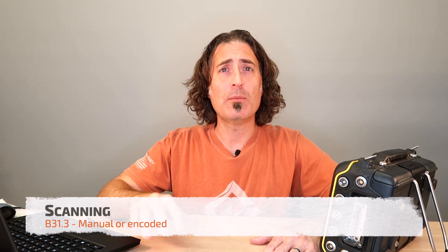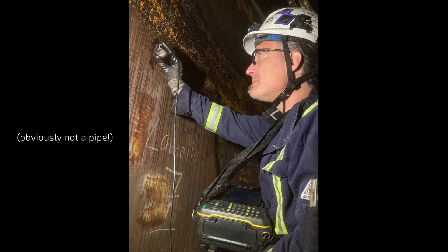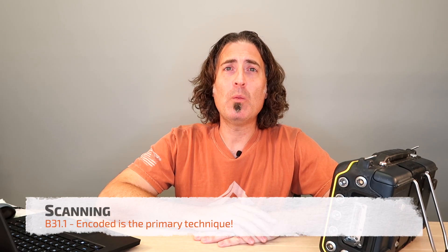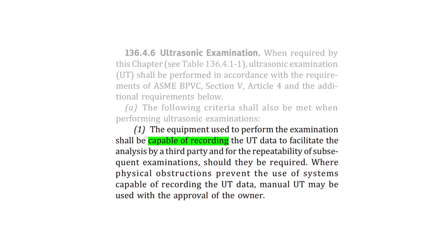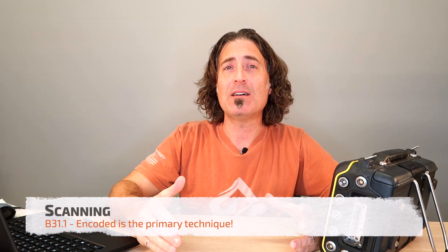Let's talk about hand scanning versus encoded. For B31.3, that's the easy one — they're actually going to let you hand scan with conventional UT or phased array, but typically what you're going to do is an encoded phased array scan. For B31.1, you have to encode. The only time they're going to let you do any hand scanning at all on a B31.1 piping weld is to cover off the areas you can't reach with the scanner.